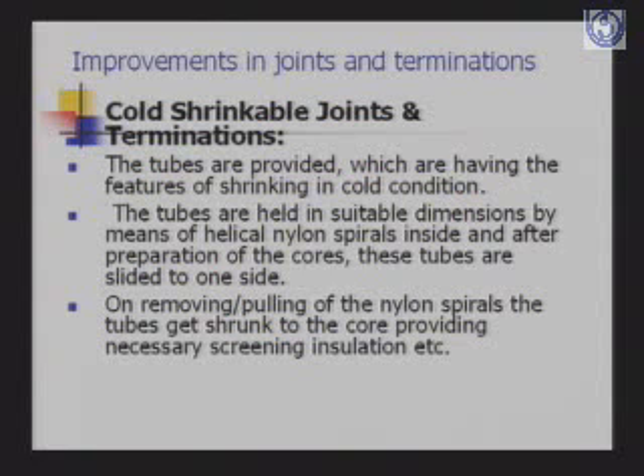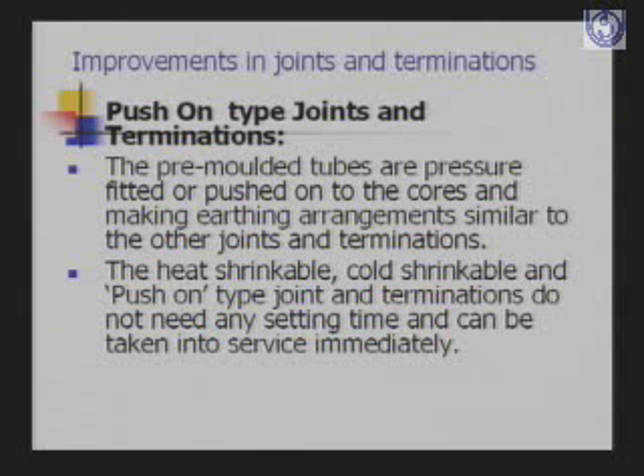The tubes are held in suitable dimensions by means of helical nylon spirals inside, and after preparation of the cores, these tubes are slid to one side. On pulling of the nylon spirals, the tubes get shrunk to the core, providing necessary insulation. Then we have the push-on type joints and terminations.